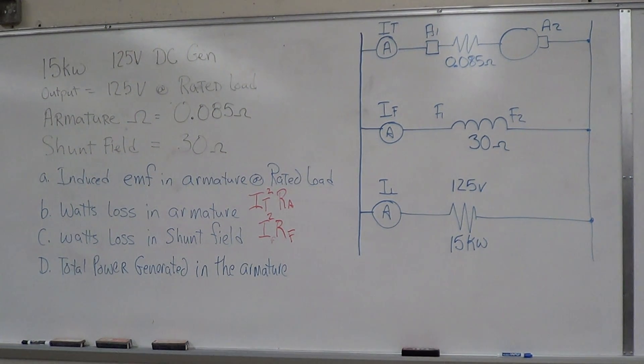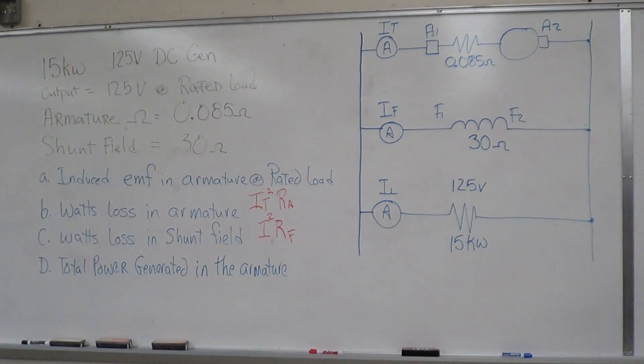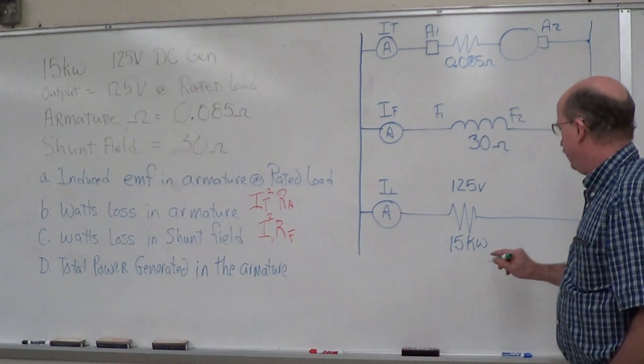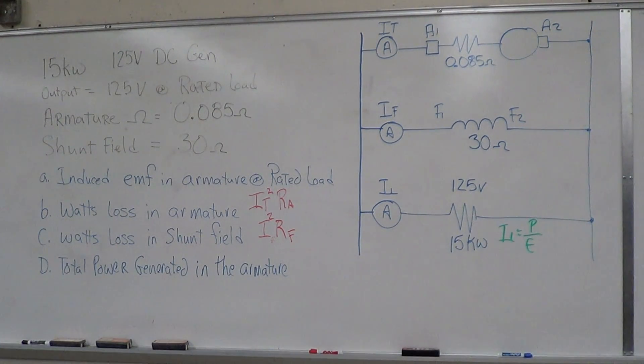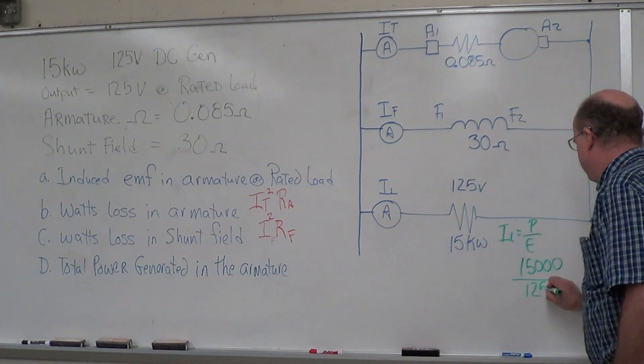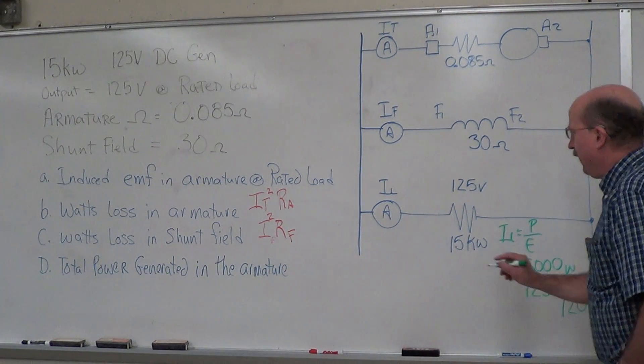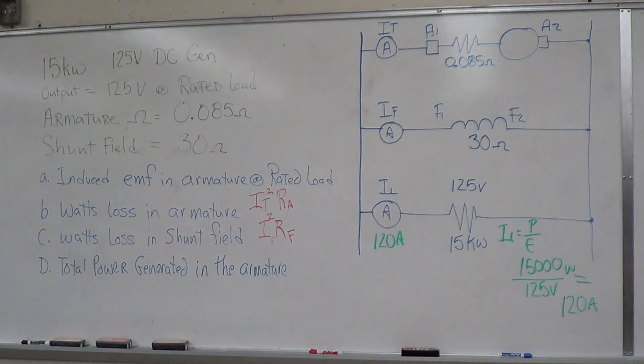Now let's work from the bottom up and talk about our currents. We've got 15 kilowatts, 125 volts. IL is going to be P over E, so 15,000 divided by 125, which gives us 120 amps.